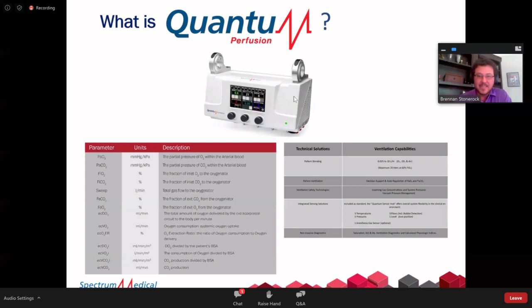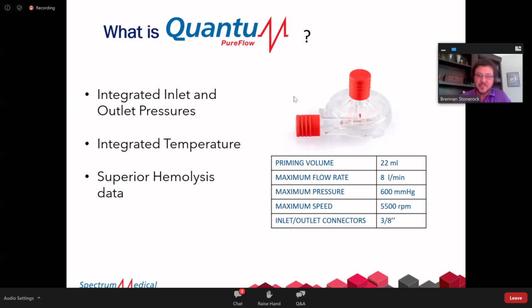So moving on to some of the disposables we were recently launching here, and talking about what the goals were when we designed a centrifugal pump. The first was a low prime volume pump that was efficient enough to support a wide range of patient populations. And as you can see, our CP22 has a potential energy to flow up to 8 liters a minute with a total pressure of 600 millimeters of mercury. The second design characteristic was to integrate pressure and temperature monitoring into the pump to eliminate the need for invasive monitoring, which are subject to clot burden, potential infection, maybe even accidental air embolus to the patient.